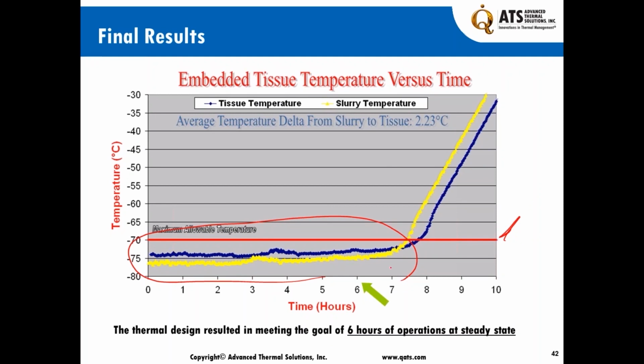And as you can see here, we were able to go to about minus 75 on average and maintain over 7 hours of steady temperature. Beyond 7.5 hours, or possibly 8 hours, we noticed that the change is made and the sample may not work properly. But we managed to exceed by something like 20% the design requirements, and by about almost 10% the temperature requirements for this design. So upfront calculations, upfront design process, and then verification as we go through.